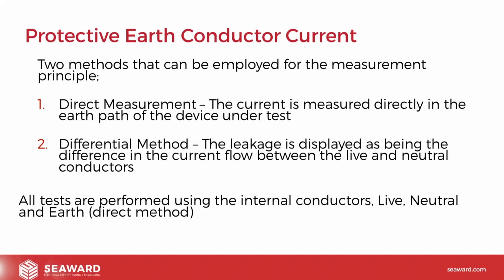So the direct measurement requires the test equipment to have an ammeter capable of reading the current flow in the earth path of the device. So very simply, you power the equipment on, and there's a measuring device that simply measures any current flowing back into the test equipment via the earth cable. To ensure a good reading in this case, it's essential the unit under test is disconnected from any sources of grounding, so we've only got the one path flowing back into it. If, for example, you had a device with an external earth connection, it's important that earth connection is disconnected, so the only path back into the instrument is via the protective conductor, i.e. the earth cable. This eliminates any secondary paths.